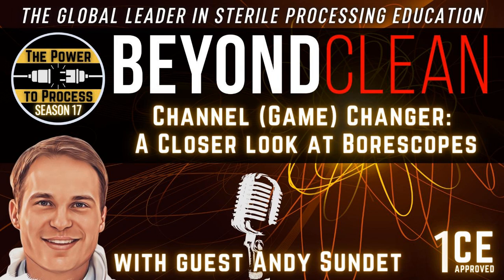So I would suggest looking at the space that you have. Do you need a computer? Do you want a computer? Do you want to capture pictures or videos? Is that going to be important for your team in training, in going back to manufacturers and asking questions about what you're seeing? That's a big question. What types of devices are you inspecting? Are they longer lumen? Meaning we're going to have a longer borescope for that. And do we have room to maybe lay out that device to even get a good visual inspection?